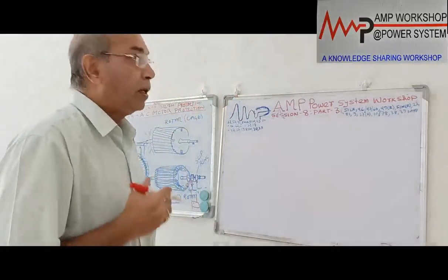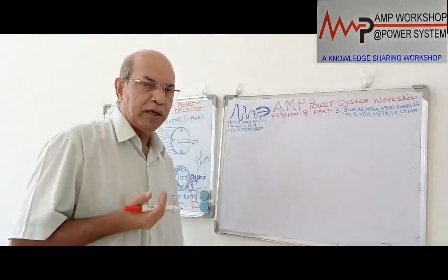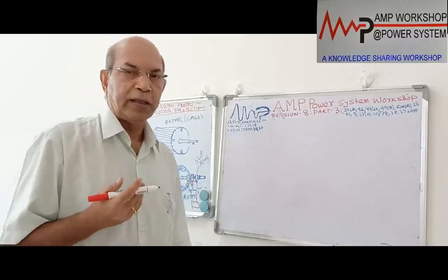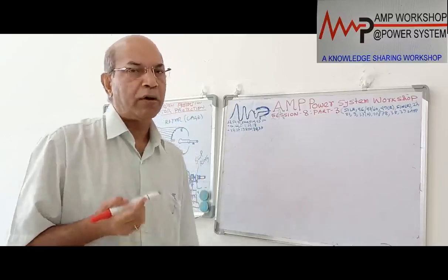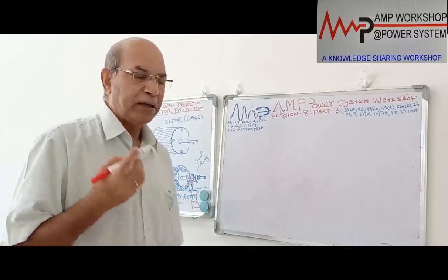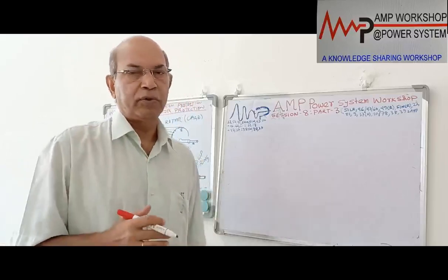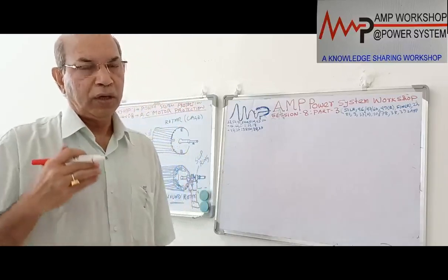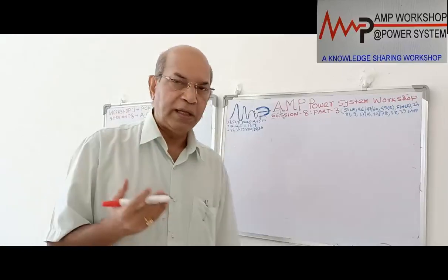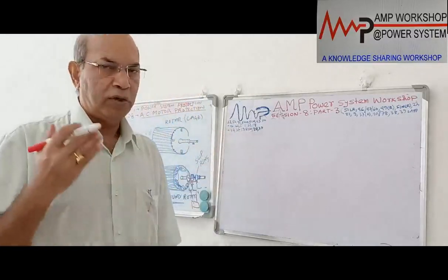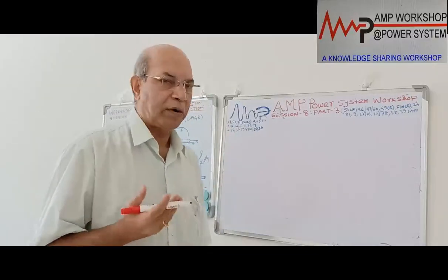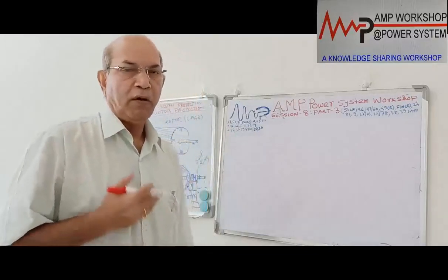Now about the rotor protection, we have discussed it already. The stator overheating protection can be done either by overcurrent protection or by a separate RTD. Now, as the rotor is rotating, working in a short circuit condition, if there is overheating in the rotor, in both cases we have seen the possibility of rotor overheating comes either from negative sequence current or unbalanced current.